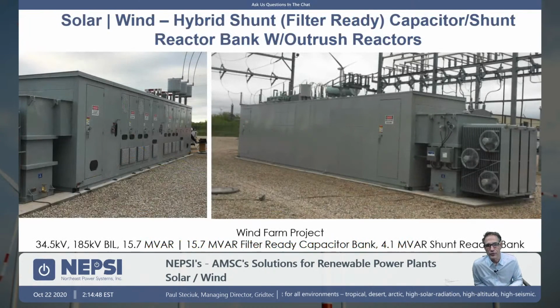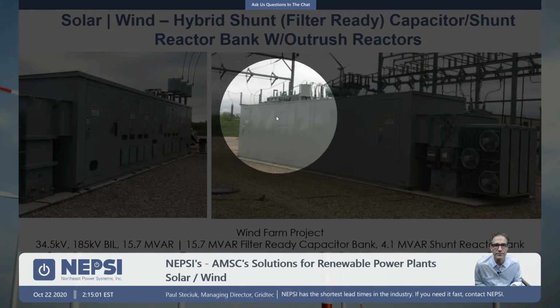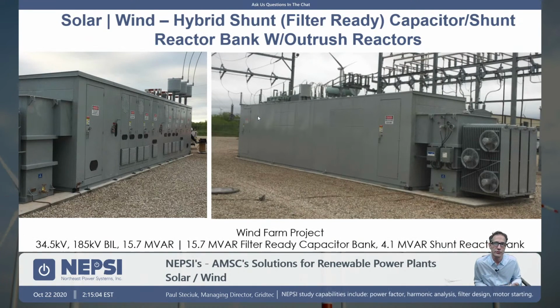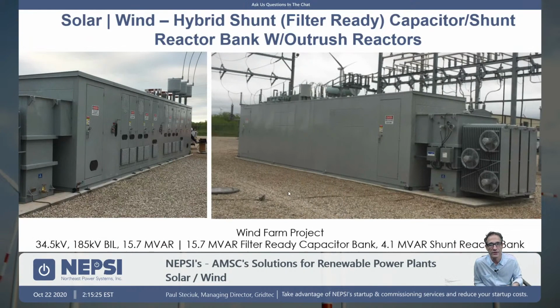So this is another project where we did a 2-stage cap bank, filter ready. You can see the filter ready concept here, and we're going to be talking more about this. These are removable panels in the back for passing through into a reactor cabinet, which would also contain a potential for aux capacitors and resistors to create filters. But if the system is filter ready and you were to start the system up and have a problem, say you have a resonance issue, we could quickly put another pad on the back here and create a harmonic filter system. And in this case, the customer would not be stuck with a capacitor bank that does not function or does not work. So that's the advantage of this system.